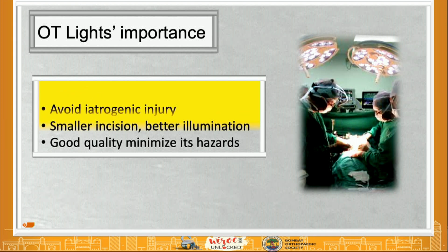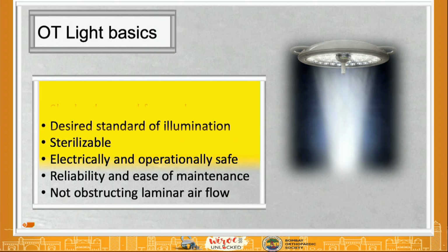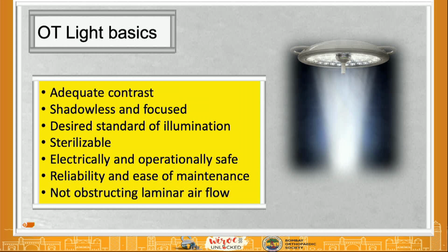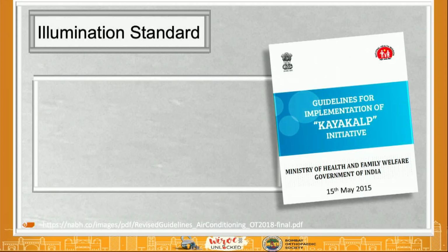So it's very important that the light should be able to give you and identify all the structures, and it should avoid iatrogenic injury. In a small incision, you should be able to do when you have got a good illumination, and of course you have to minimize the hazards. Regarding the basics, it has to have an adequate contrast, shadowless, focused with a desired range of illumination, sterilizable, electrically and operationally it should be safe. And it should have ease of maintenance, and it should not obstruct the laminar airflow.